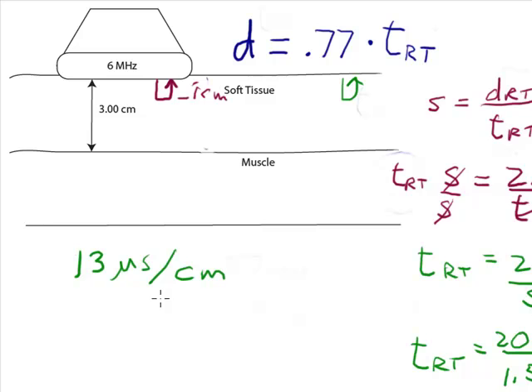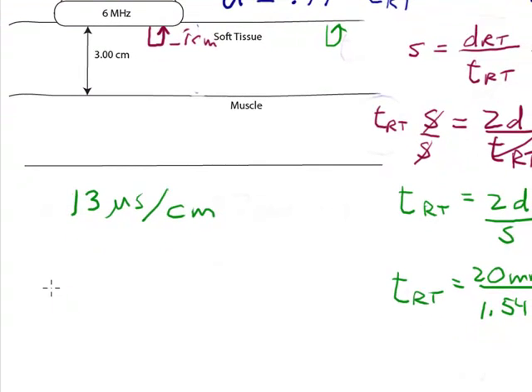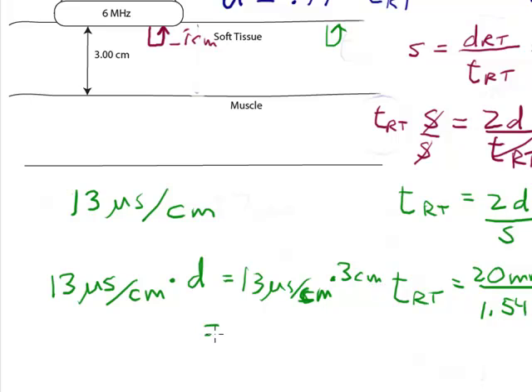If the sample is 2 cm away, it's going to take 26 microseconds. Let's look at this example where the reflector is 3 cm away. All I have to do is use my rule of 13 microseconds per centimeter times the distance in centimeters. That's 13 microseconds per centimeter times, in this case, 3 cm.